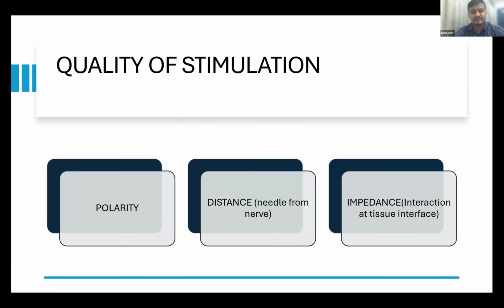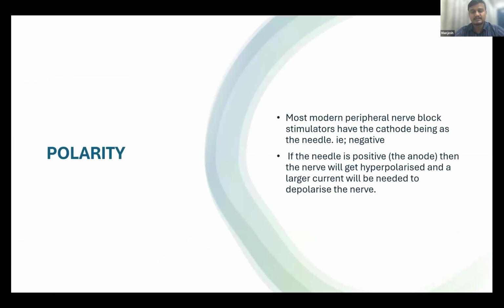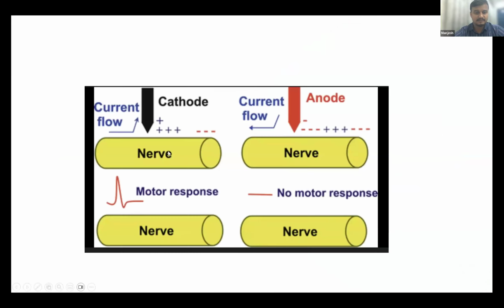Coming to the quality of stimulation, it is guided by three main concepts: the polarity, the distance of the needle from the nerve, and the impedance or resistance, that is, the interaction at the tissue interface. Coming to the concept of polarity, most modern peripheral nerve block stimulators have the needle as the cathode. That is, the tip of the needle will be negative. If the needle is positive, then the nerve will get hyperpolarized and a larger current will be needed to depolarize the nerve. This is the pictographic example for polarity. If the needle tip is the cathode, it will give rise to a motor response with less duration or less current intensity. But if the same needle tip is the anode, it will not give rise to a motor response at that same current intensity.